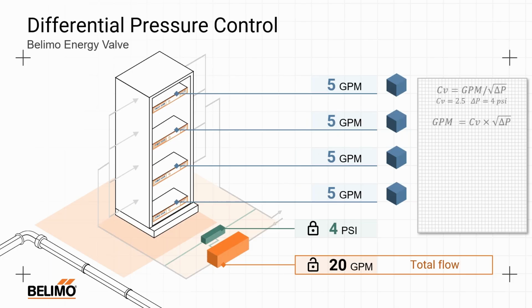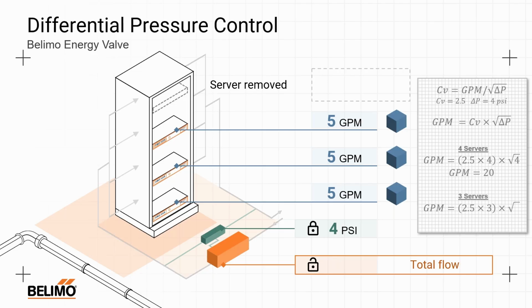So we take the flow coefficient formula, the same parameters of flow coefficient. This time we're going to solve for GPM because that's what we're most interested in now. So GPM equals the flow coefficient times the square root of the pressure drop. With 4 servers in place and 2.5 Cv per server, the math still works. It's 2.5 times 4 times the square root of 4, and we have 20 gallons a minute. Forwards and backwards, the math still works. But here's why we get the right flows we want when we hold on to that 4 psi. With 3 servers in place, I now get 2.5 times 3 times the square root of 4, and I'm getting that 15 gallons a minute exactly how I want to.